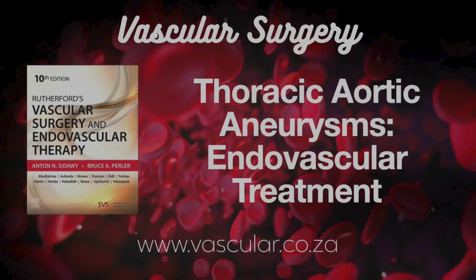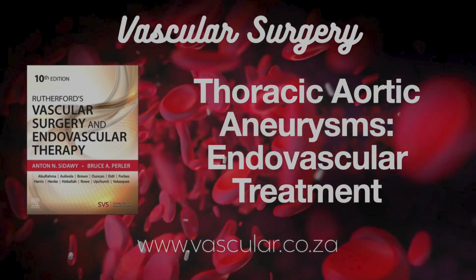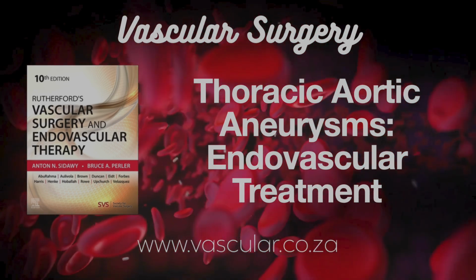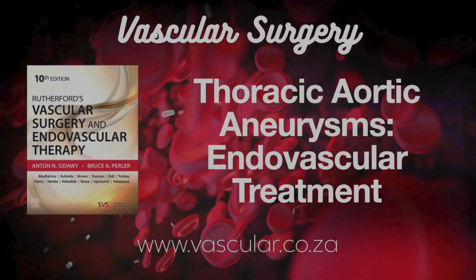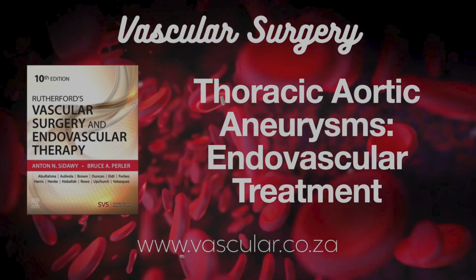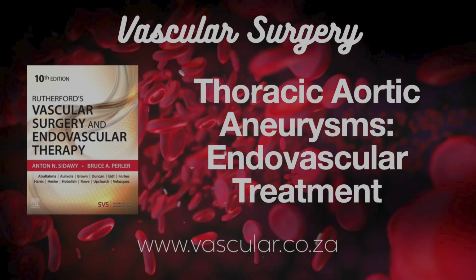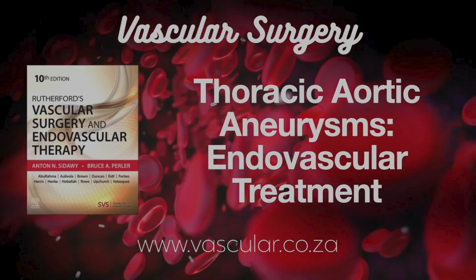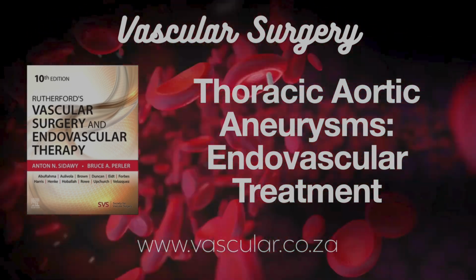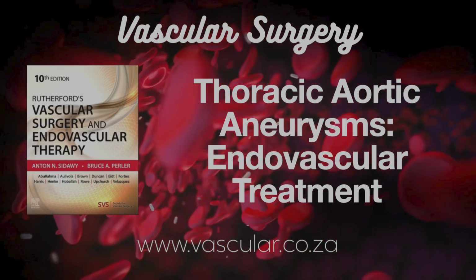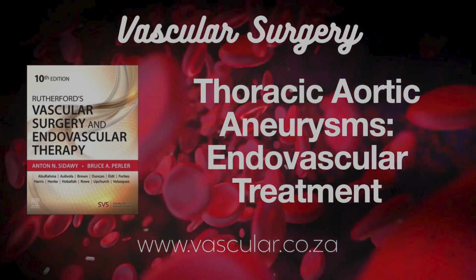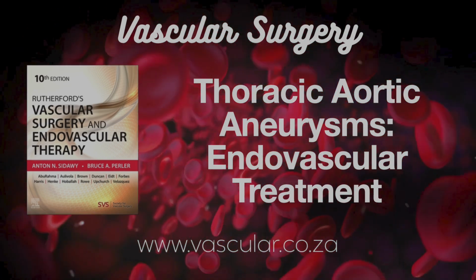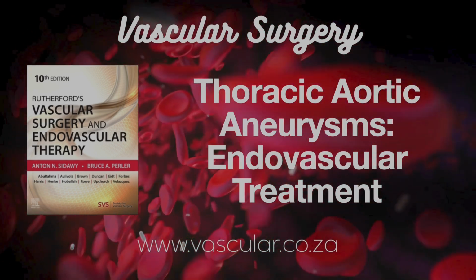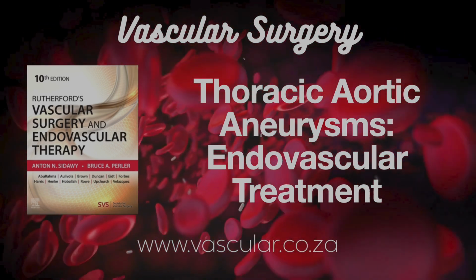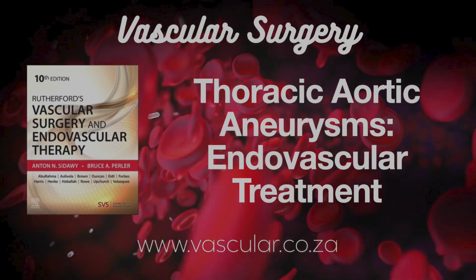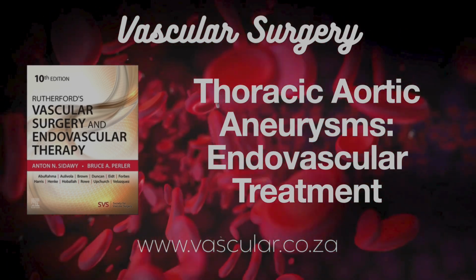Good. And finally, the Terumo Aortic Relay Device Plus. Approved September 2012. Right. This is the third generation of what used to be the Bolton Relay. It's a one-piece graft, woven polyester on self-expanding nitinol stents. Key features. It has a pre-curved nitinol support strut for stability and conforming to the aorta's curve. Hydrophilic braided outer sheath for delivery. Comes in bare stent for active fixation and non-bare stent versions. Straight and tapered designs. Recommended oversizing is 10% to 15%.